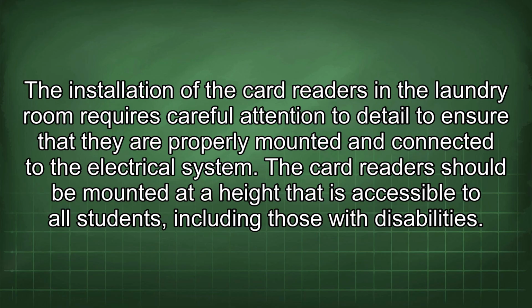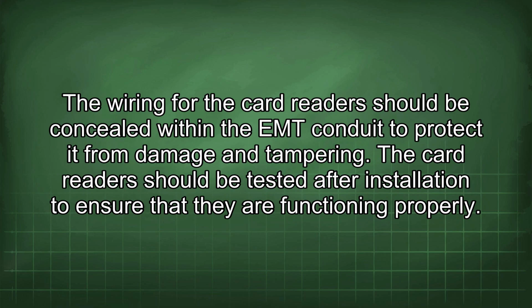The installation of the card readers in the laundry room requires careful attention to detail to ensure that they are properly mounted and connected to the electrical system. The card readers should be mounted at a height that is accessible to all students, including those with disabilities. The wiring for the card readers should be concealed within the EMT conduit to protect it from damage and tampering. The card readers should be tested after installation to ensure that they are functioning properly.